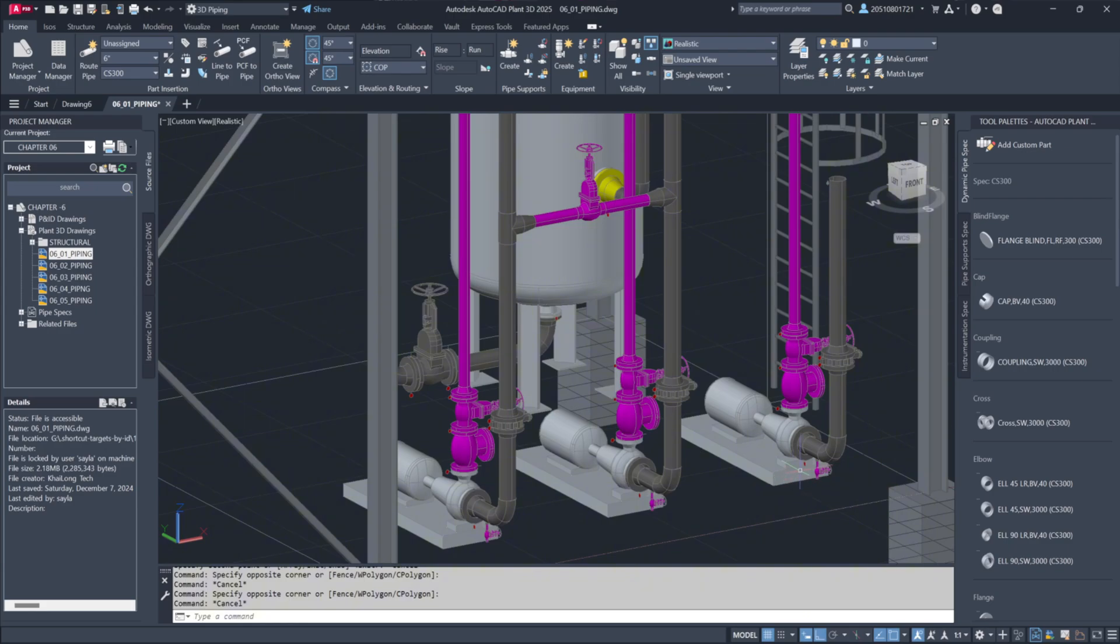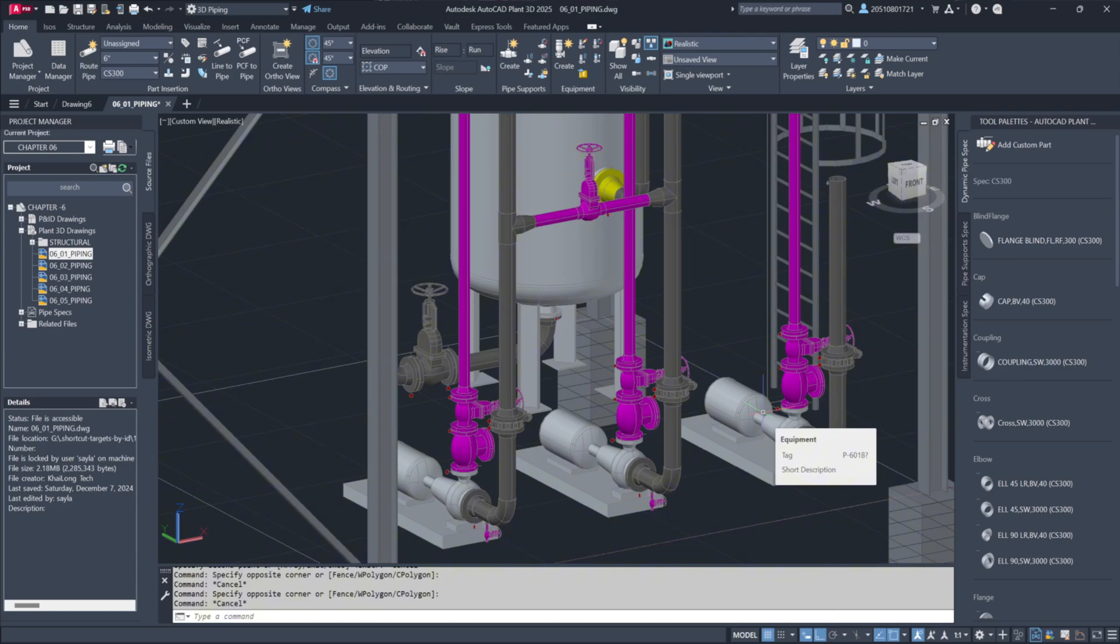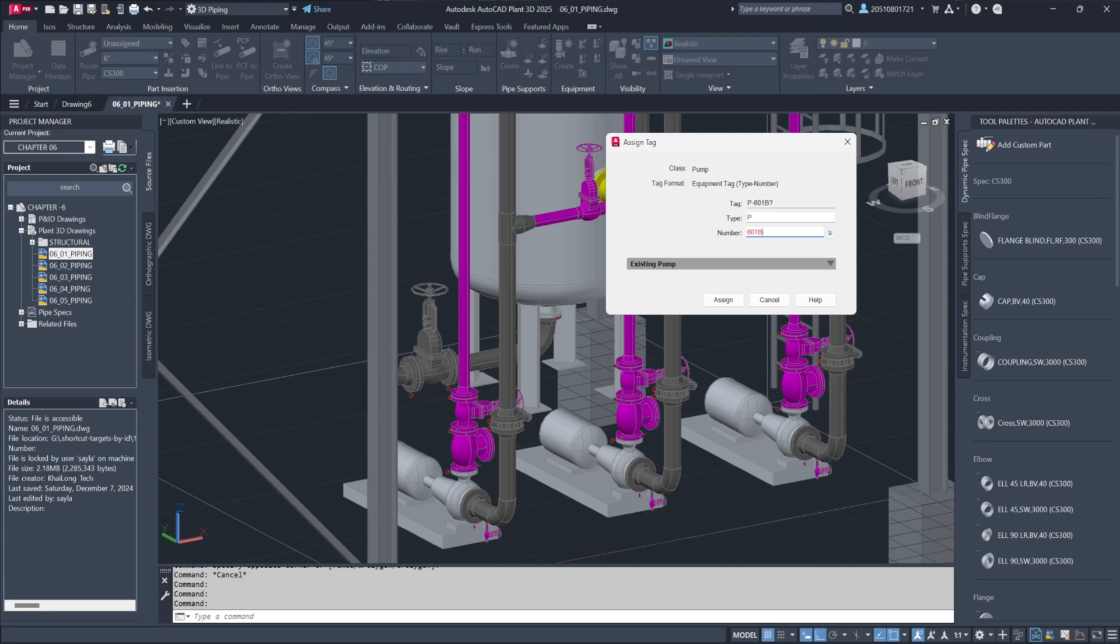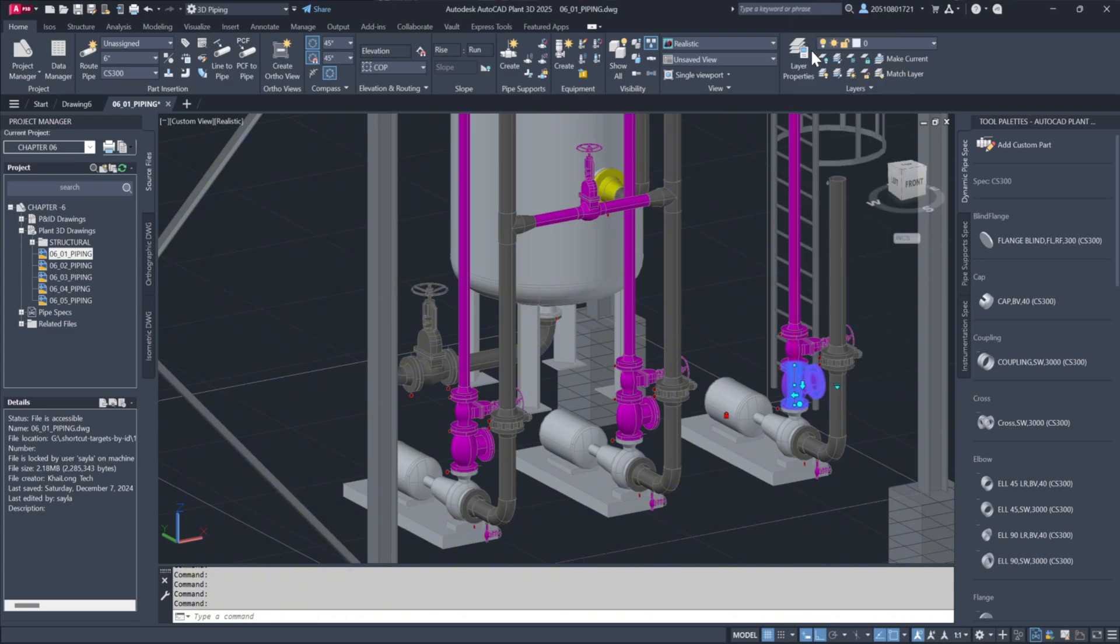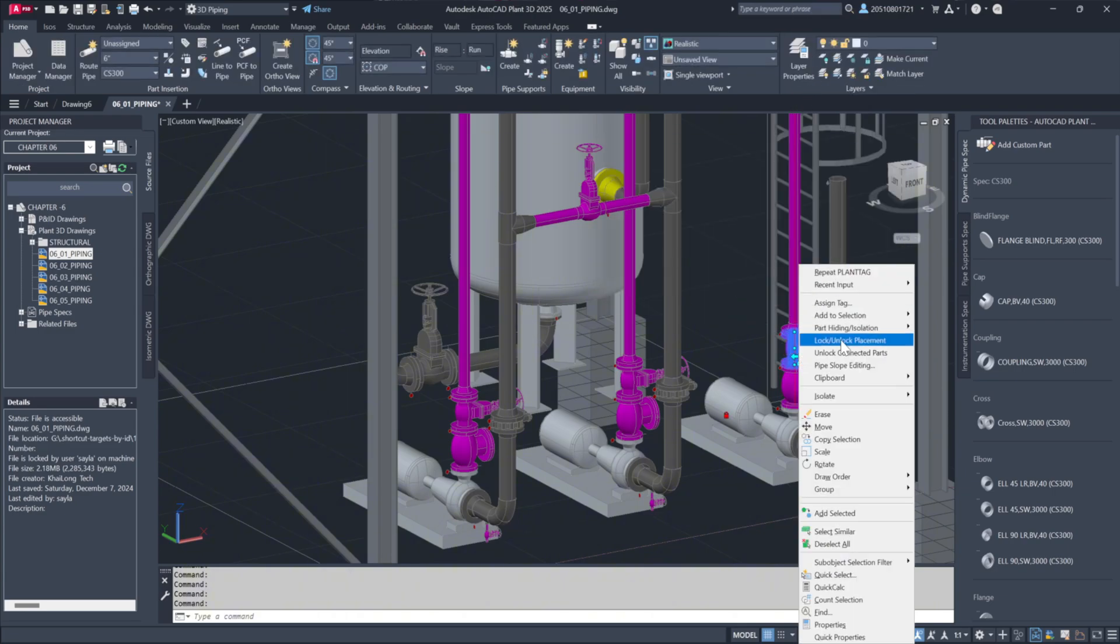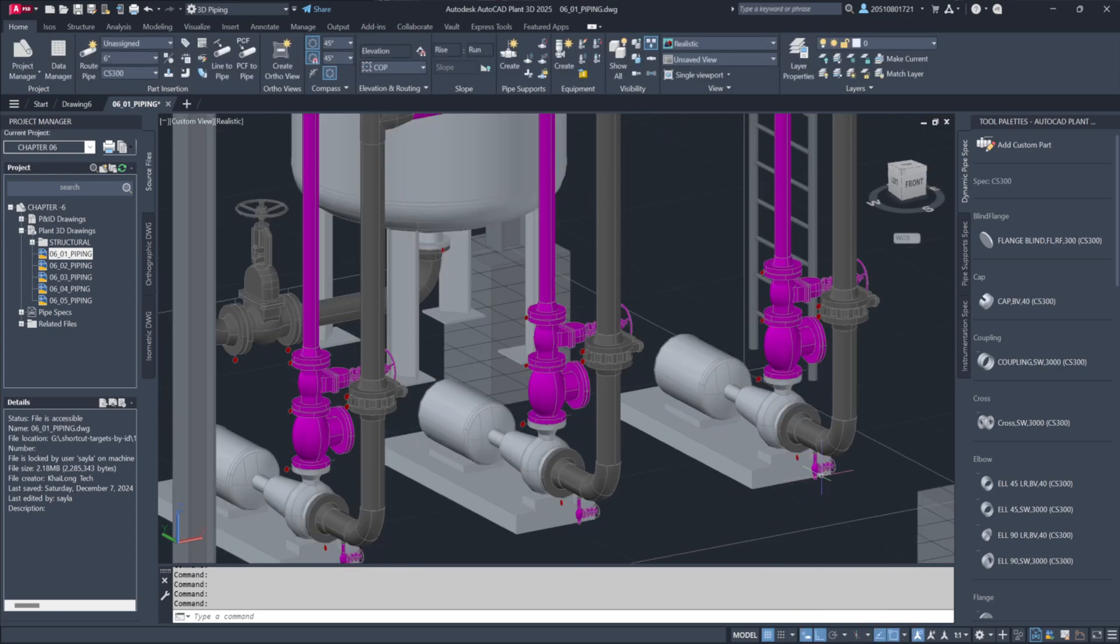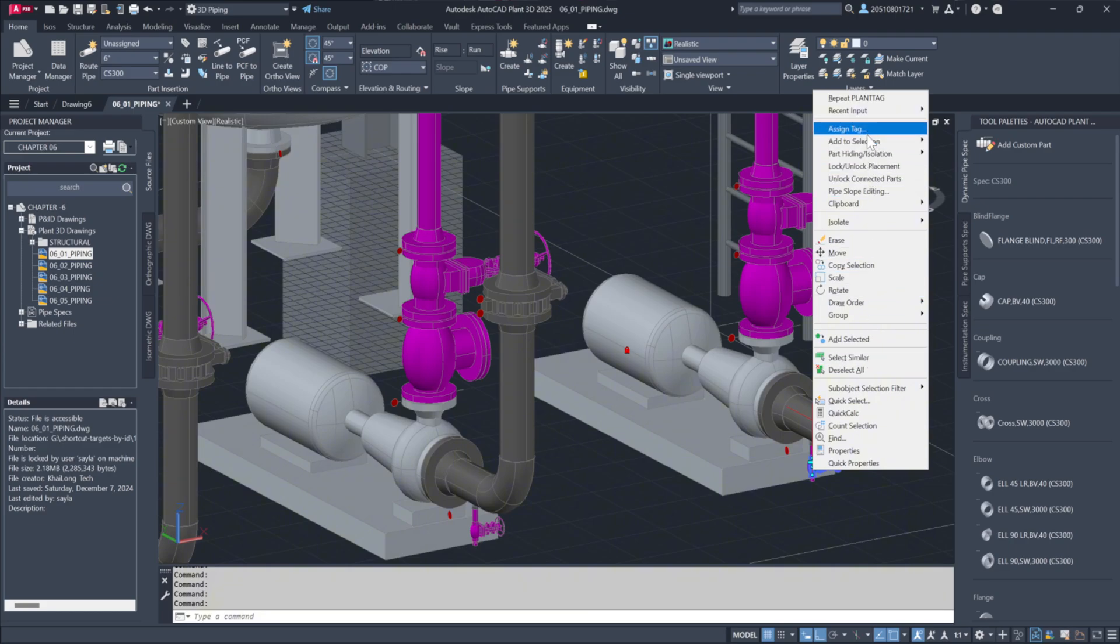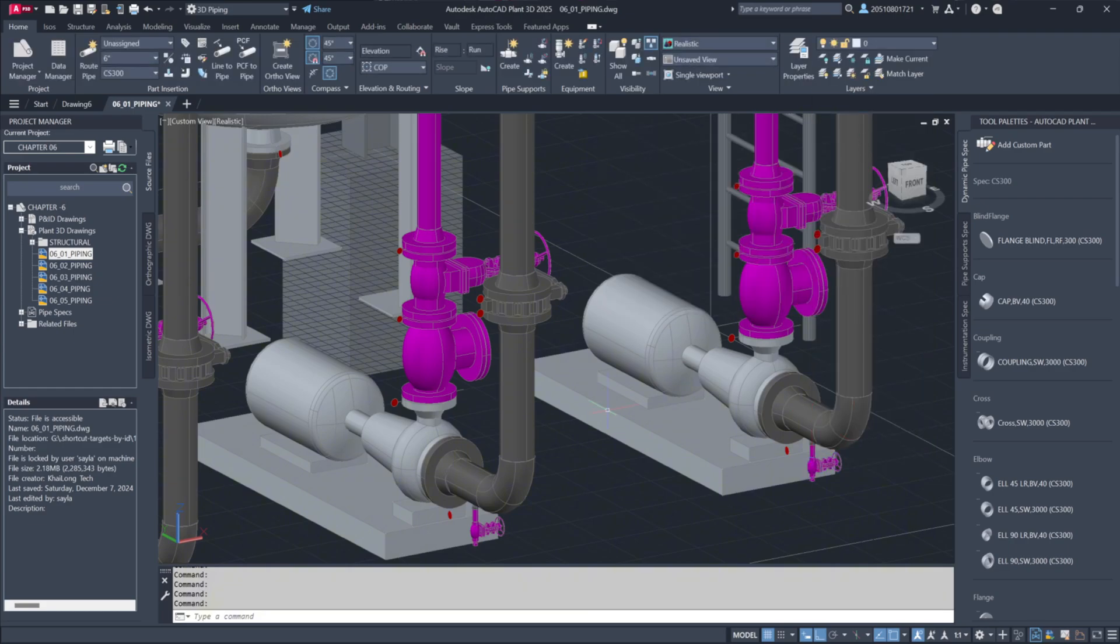Next, let's check our pump tags. Currently, we have pumps labeled 601A and 601B, but the copied pump shows a 601B question mark tag. I'll rename it to 601C by accessing the properties panel and updating the tag data. We'll need to update the valve tags as well. By right-clicking, selecting Assign Tag and choosing the next available number, I'll update all valves in the new configuration. Don't forget the small drain valve, which can be adjusted similarly.